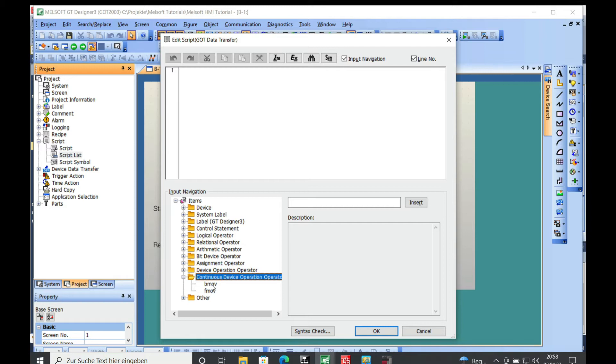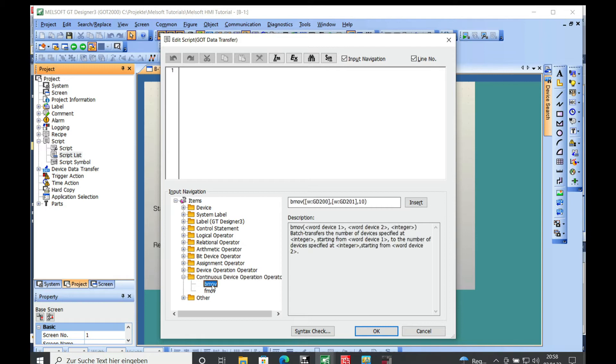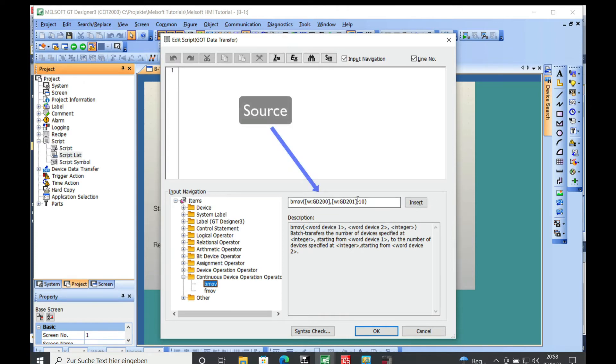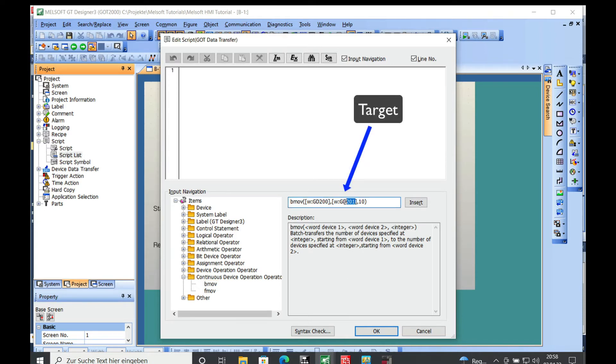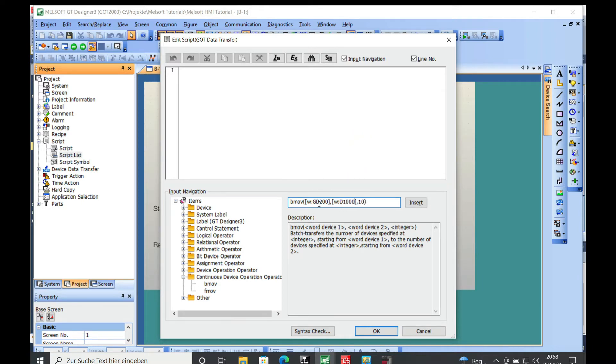Then you just double click on this block move right here and you already got a description open where you can see how the script is gonna be working. I'm gonna leave the GD200 as the starting address and I'm gonna put the D1000 in, in order to transfer this data from the GD200 to the D1000 in the PLC.